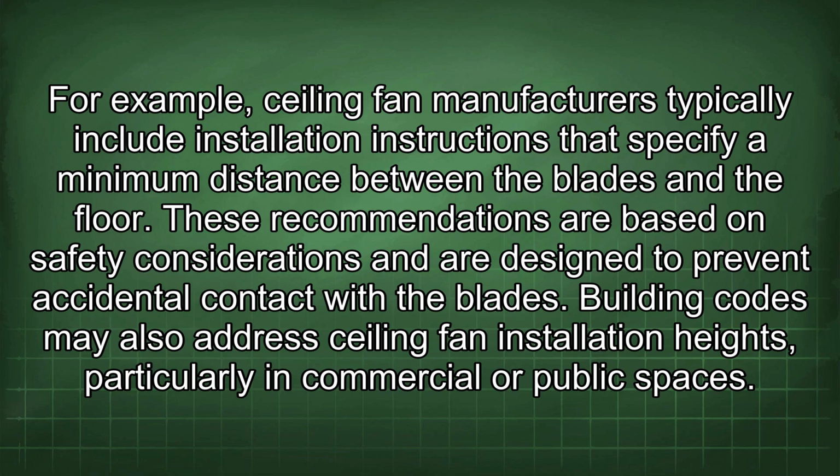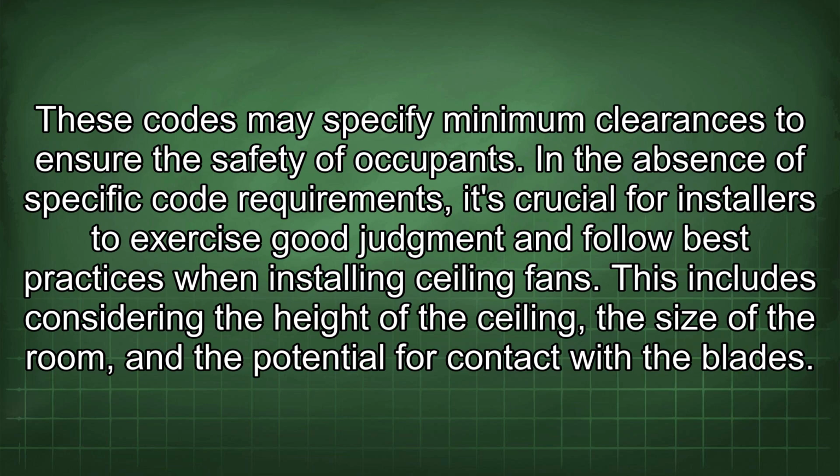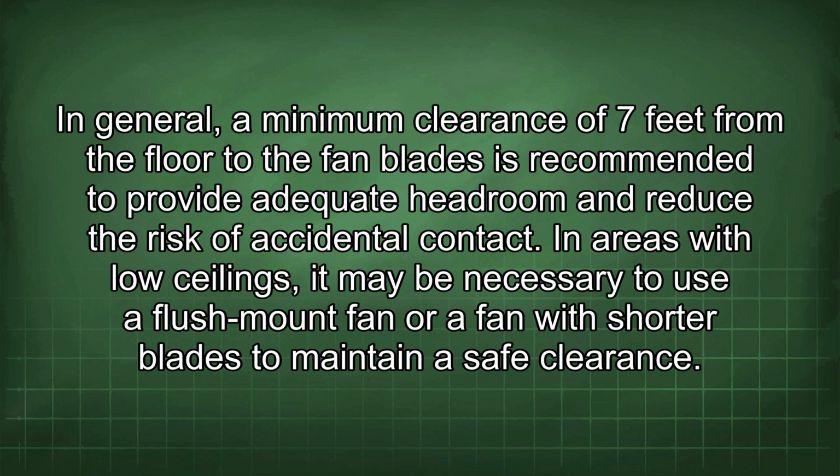Building codes may also address ceiling fan installation heights, particularly in commercial or public spaces. These codes may specify minimum clearances to ensure the safety of occupants. In the absence of specific code requirements, it's crucial for installers to exercise good judgment and follow best practices when installing ceiling fans. This includes considering the height of the ceiling, the size of the room, and the potential for contact with the blades. In general, a minimum clearance of 7 feet from the floor to the fan blades is recommended to provide adequate headroom and reduce the risk of accidental contact.